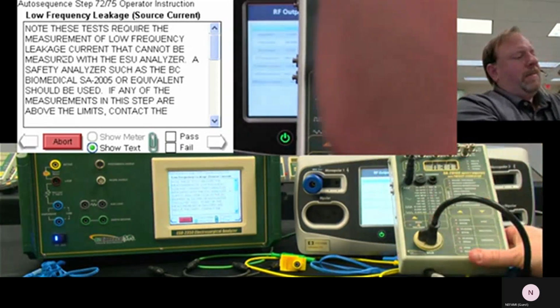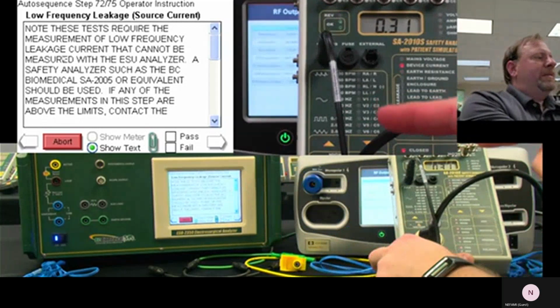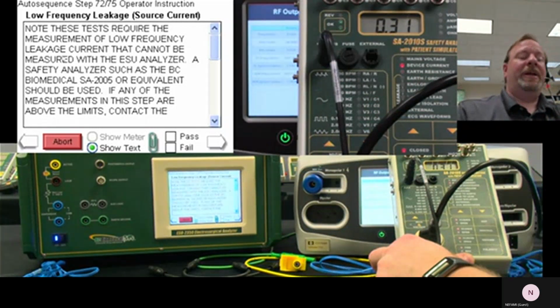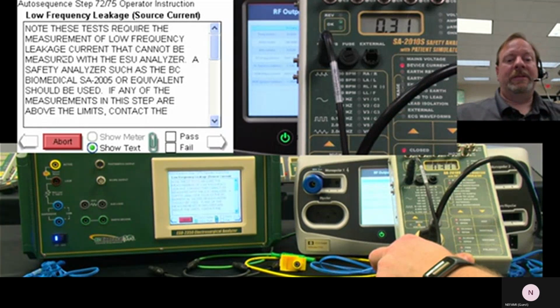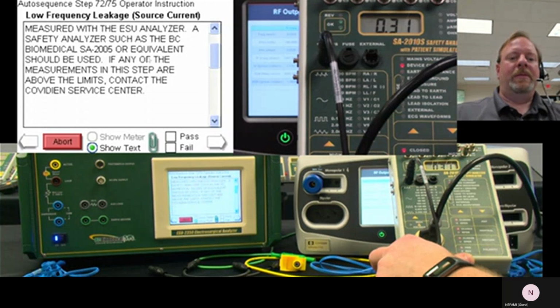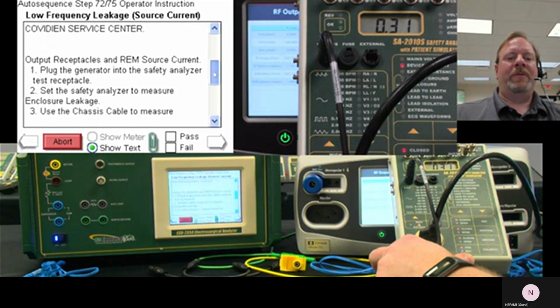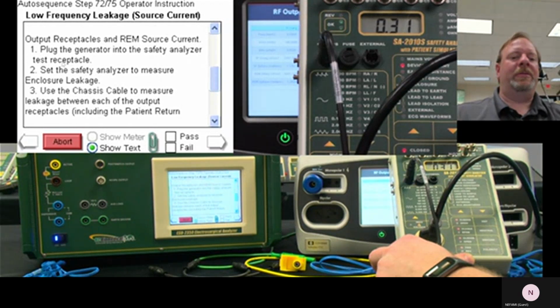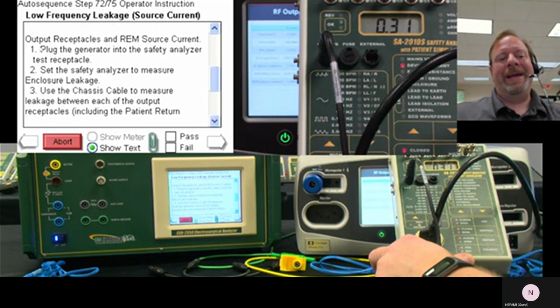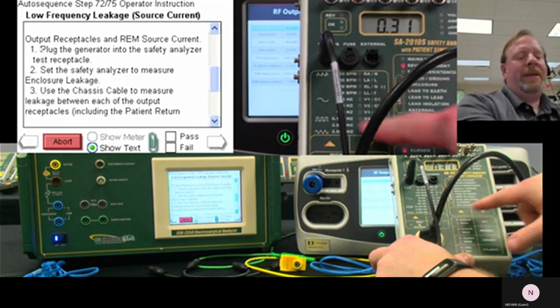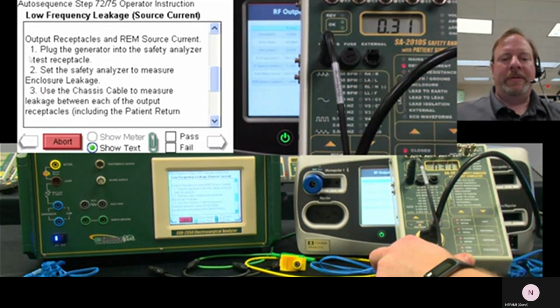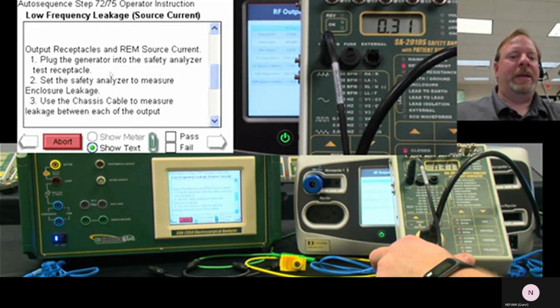In any case, the 2350 does all the high frequency stuff, power measurements, but it can't do the low frequency measurements, 60 hertz safety testing. So it mentions a BC Biomedical SA 2005. The reason we need that is for the lead isolation test, which we'll be doing in a little bit. But you can use the 2005, the 2010, or the 2010S. The S has the built-in safety or patient simulator, so it can do ECG simulations for other things. Slight little plug for the 2010S.